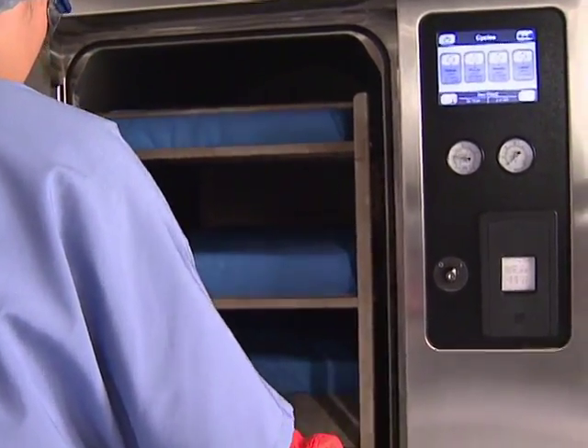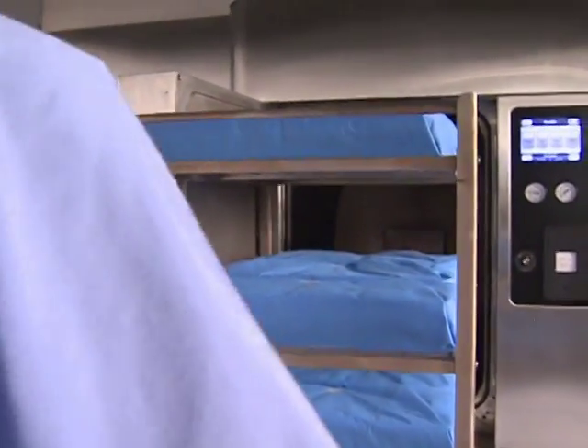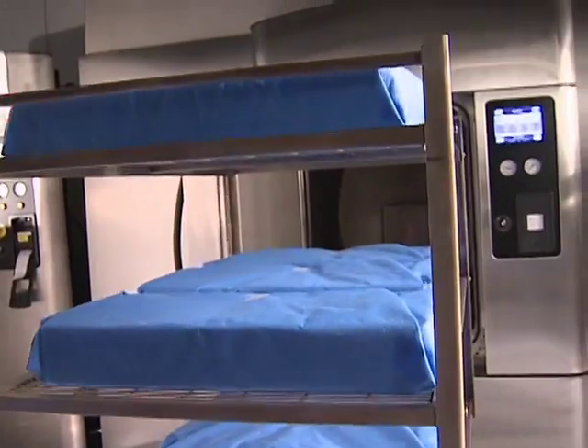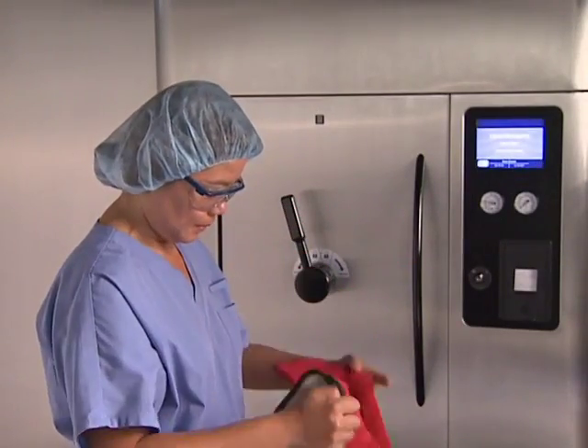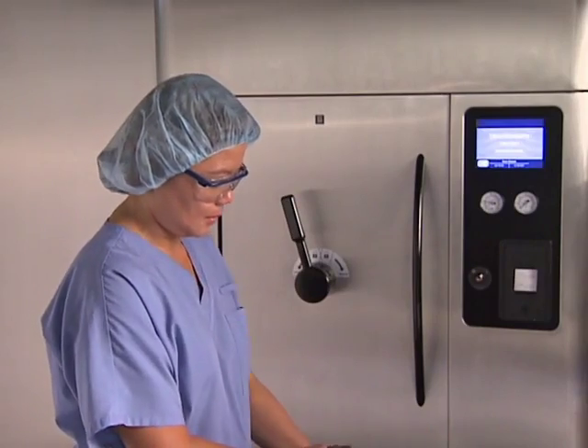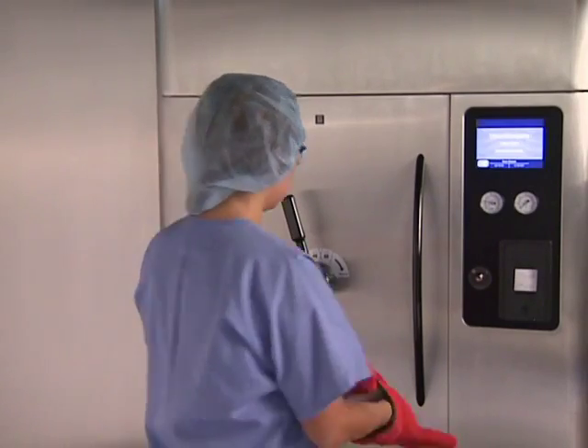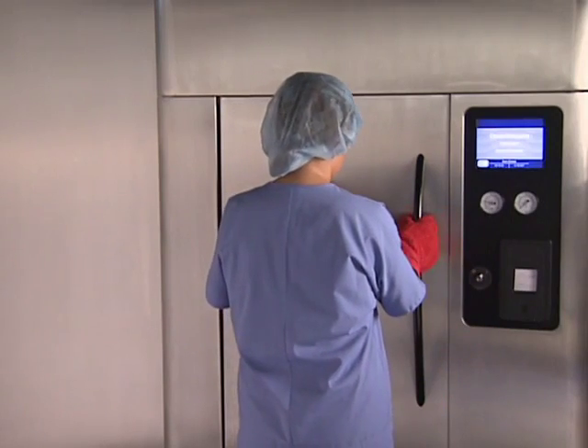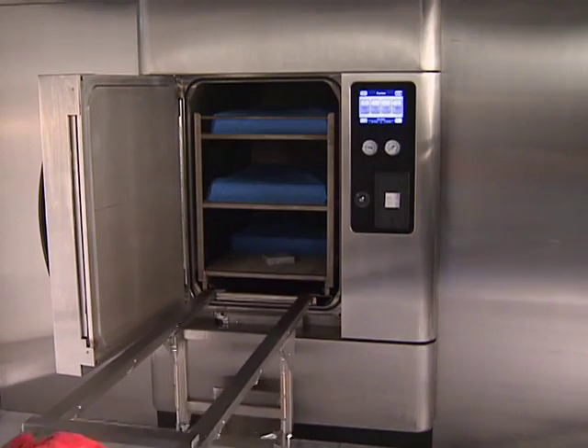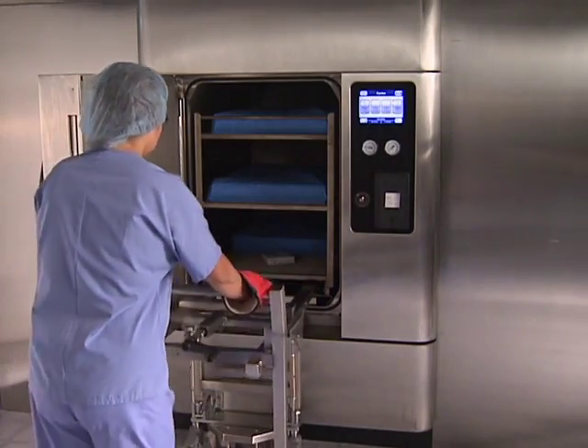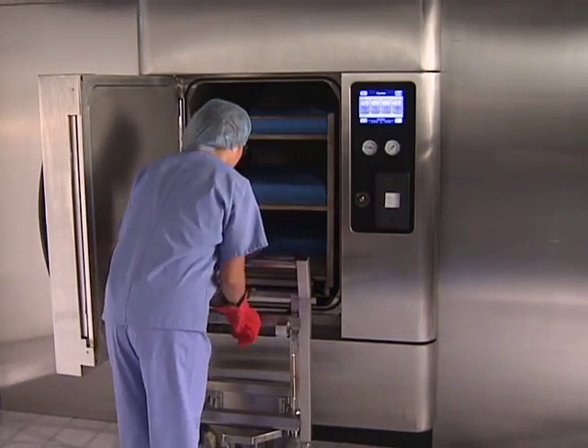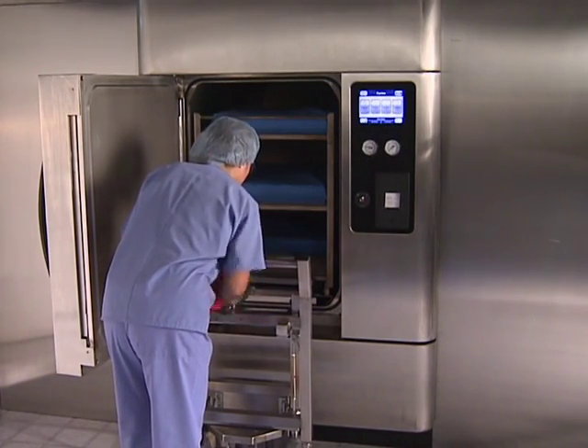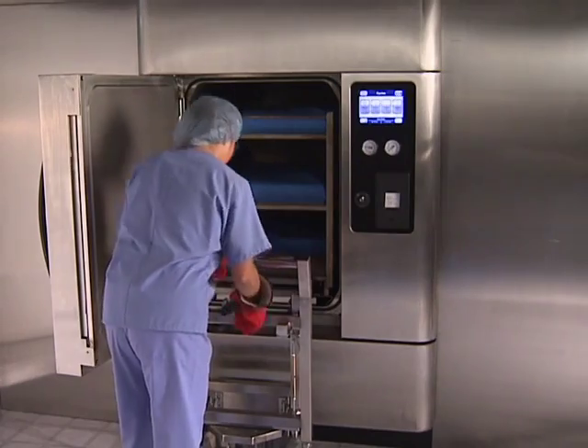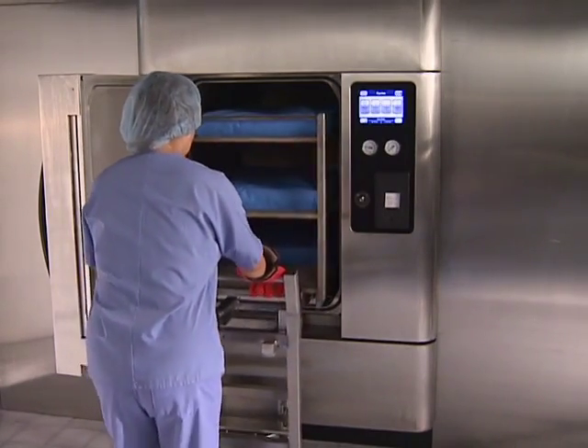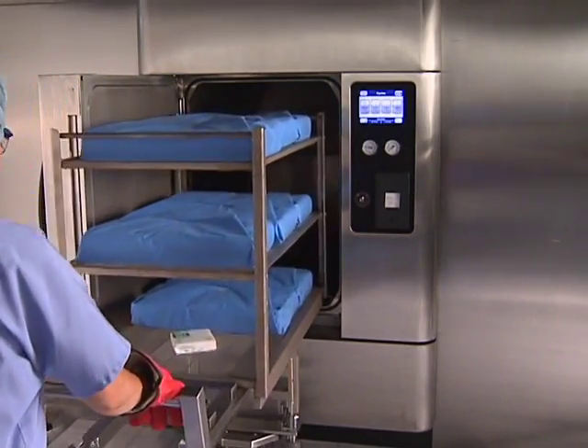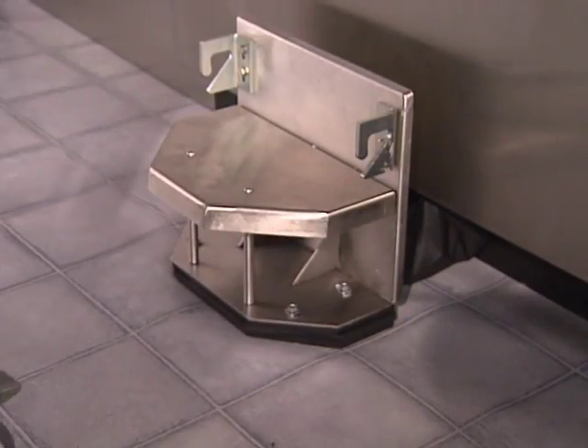The loading car and transfer carriage were designed so that there is no need for the operator to come into contact with the hot loading car when unloading the sterilizer. However, because the sterilizer, shelves, and loading car will be hot after each cycle, you should always wear personal protective equipment when removing a processed load. Move the transfer carriage forward until it engages with the dock. Push the transfer carriage fully into the chamber. Turn the hand crank clockwise until it stops and the loading car is fully lifted from the supports in the chamber. Pull the loading car and transfer carriage away from the chamber. When fully withdrawn from the chamber, the transfer carriage will disengage from the dock.